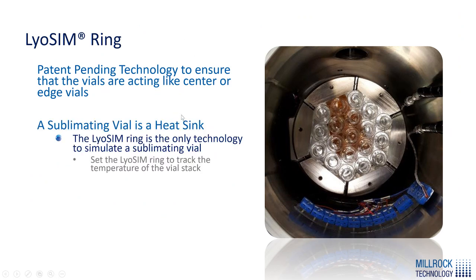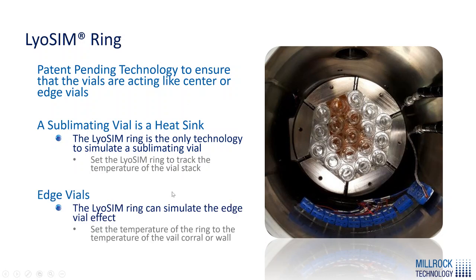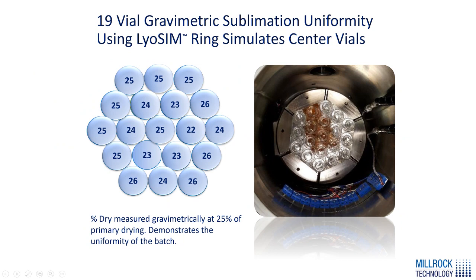The LyoSIM ring can simulate either center vials or edge vials. If we run the LyoSIM ring tracking the product temperature, we simulate center vials. If we run it above the product temperature to look like the corral that would normally be there, we simulate edge vials — a very powerful tool. When simulating center vials, we get a very uniform distribution across the batch, almost exactly what you would get for center vials in any batch. Center vials are all vials except for the outer two to three rows, which run at a higher sublimation rate. This gives us the ability to simulate 95–98% of the vials that are center vials.